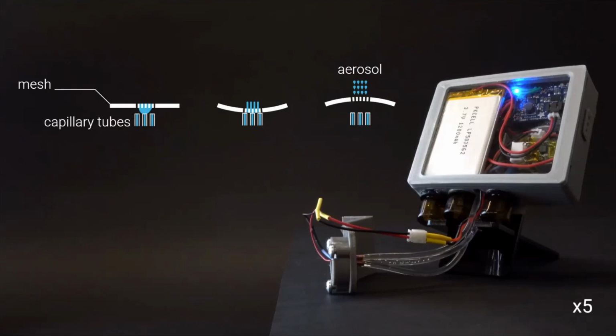Most of the time, when devices use vibrating mesh transducers, they use wicks, which are prone to cross-contamination, so you have to use one per channel or per compound. In our case, we actually used separate tubings for each of the channels, which arrive at the vibrating mesh transducer, and then attach a small capillary tube at the end that's incredibly narrow and creates a surface tension of the inner liquid that won't allow other samples to backflow into another channel.